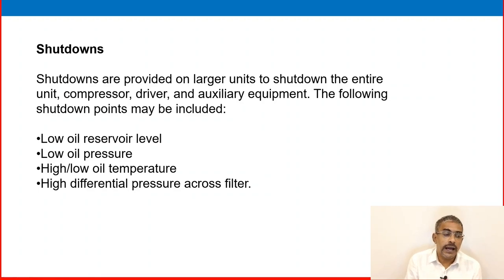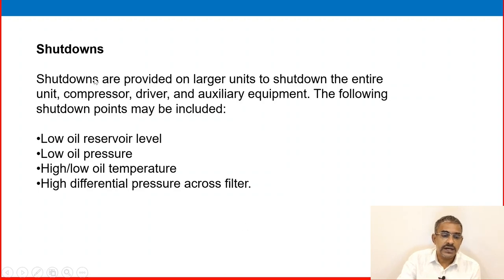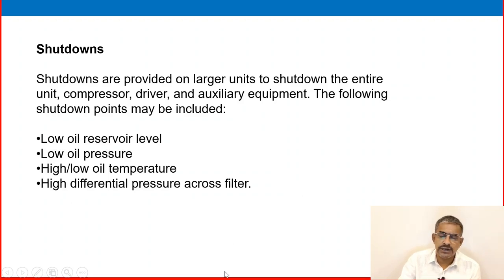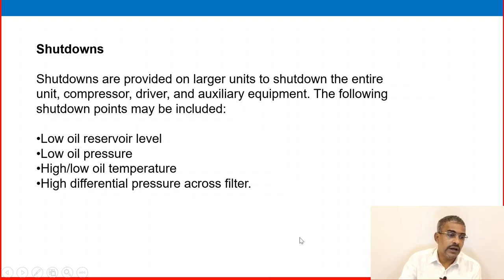Alarms indicate deviation from set points, and shutdowns activate on high-high or low-low conditions to protect the compressor. Shutdown points typically include: low oil reservoir level, low oil pressure, high or low oil temperature, and high differential pressure across the filter. On larger units, shutdowns cover the entire unit including the compressor, driver, and auxiliary equipment. External safety systems such as instrument air pressure and fire and gas detectors are also incorporated.